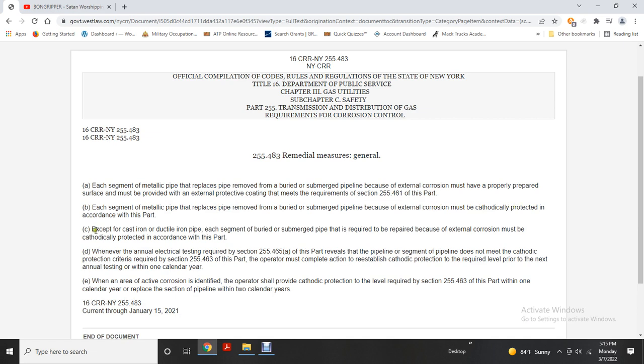Cathodic protection — remediation: except for cast iron and ductile iron pipe, each buried and submerged pipe segment required to have external corrosion protection must be cathodically protected. Whenever annual electrical testing required by Section 255.465(a) reveals that a pipeline segment does not meet cathodic protection criteria required by Section 255.463, the operator must complete action to reestablish cathodic protection to the required level prior to the next annual testing. When an area of active corrosion is identified, the operator shall provide cathodic protection at the level required by Section 255.463 within one calendar year, or replace the section of pipeline within two calendar years.